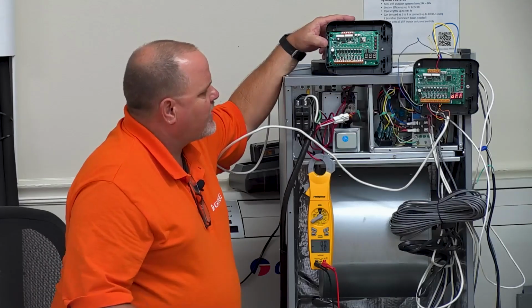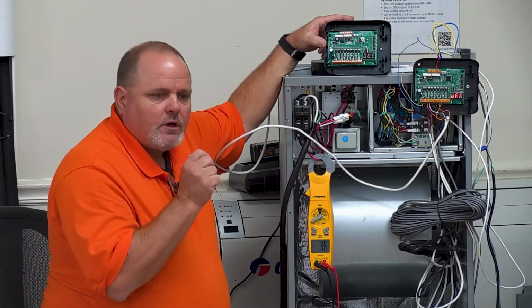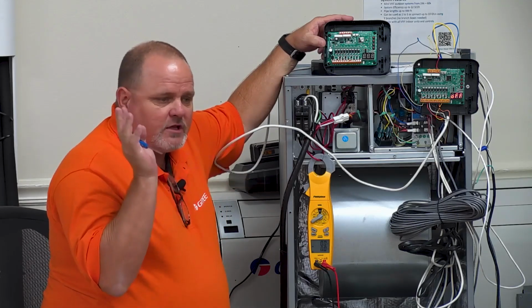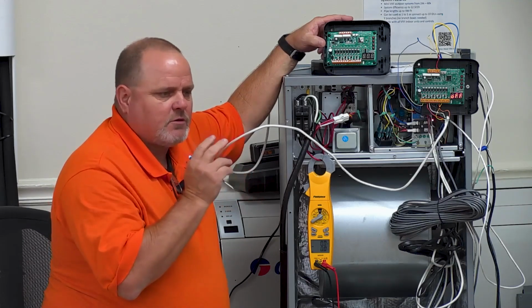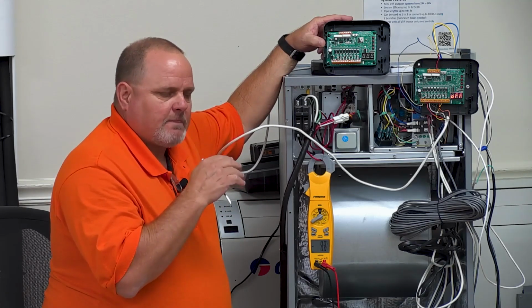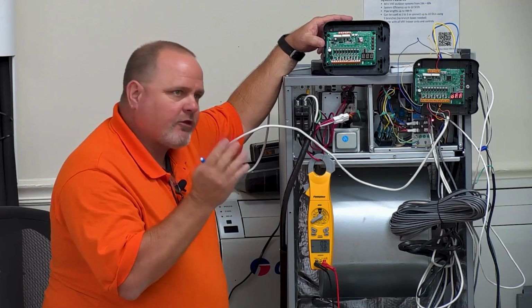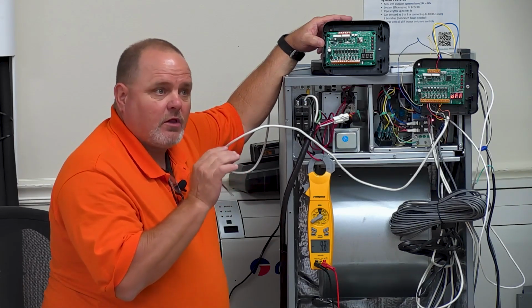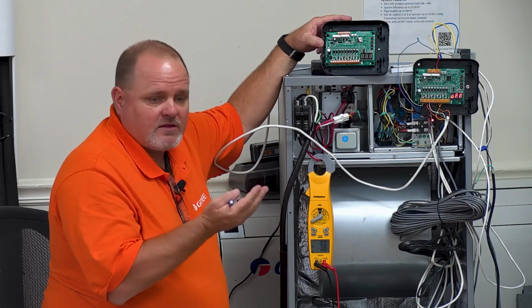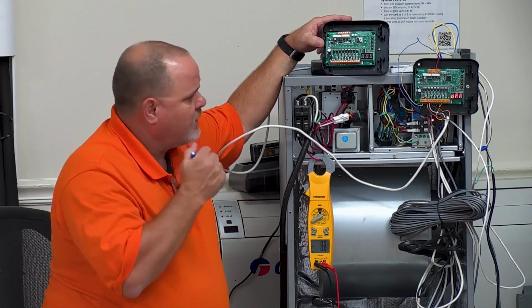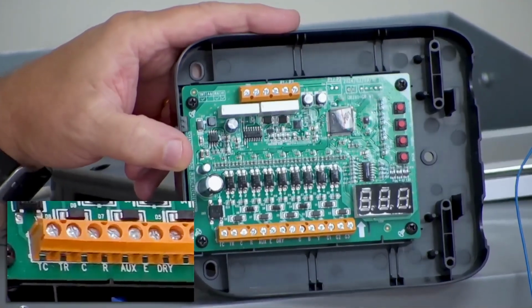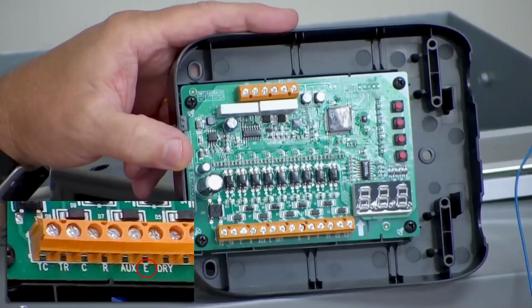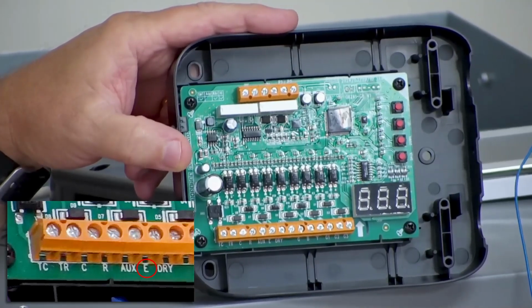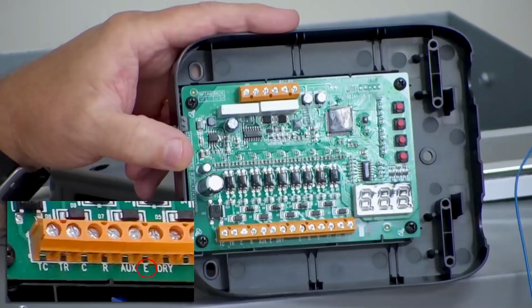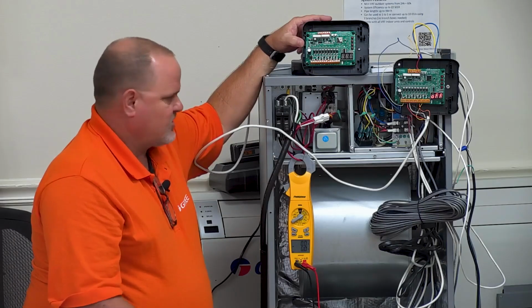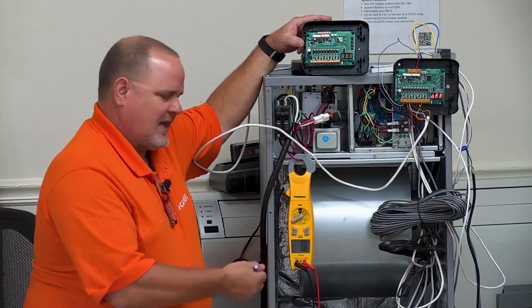So your E terminal. If you take whatever heat pump thermostat you want to use with this, and you give it an emergency heat call, a lot of thermostats share the auxiliary along with the E terminal, so it may be the same terminal within your thermostat. It depends on the manufacturer. But the minute this thing gets 24 volts to E, it will bring on the electric heat. It doesn't even have to have a G call. The way the board's programmed, it'll automatically turn on the blower if you get an E heat call. It's not going to hurt if you get a G call as well, but it's not needed either.